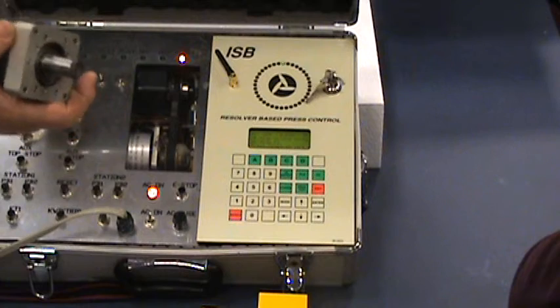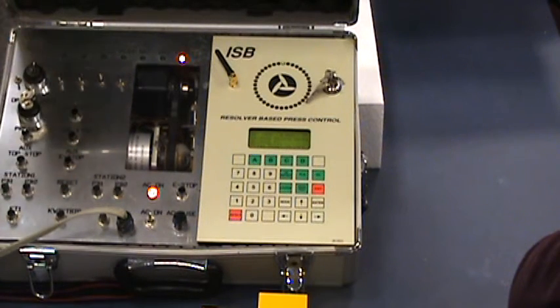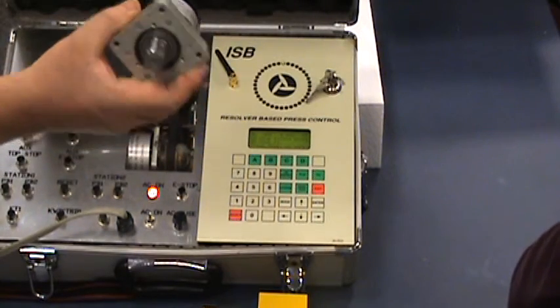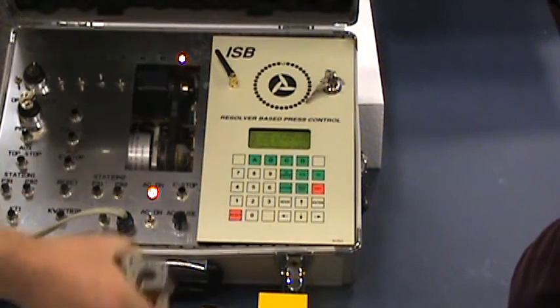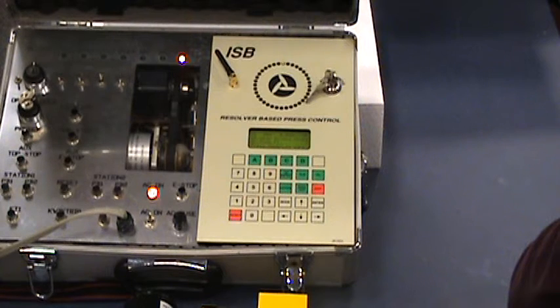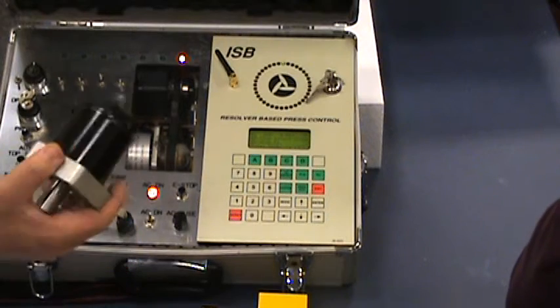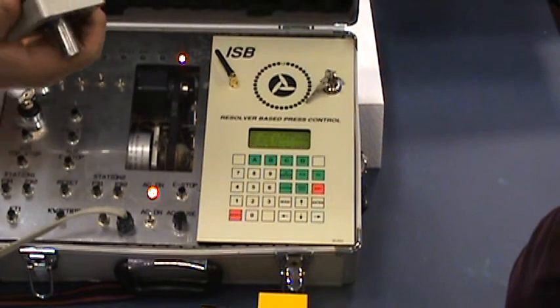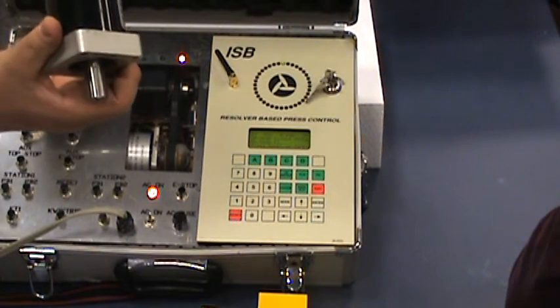So this is why we're relying on the cam box to be your pillow block or create a pillow block arrangement. Or if you're using a rubber timing belt with cog teeth, there's never going to be enough axial load on a three eighths inch resolver. But anything else, Lovejoy coupler, sprocket and chain drive, where you're direct coupled to the end of the shaft, you definitely want to go with this, because this can handle in excess of a hundred pounds of axial load. The bearing is just that much more massive. You can help yourself by mounting these on spring-loaded bases, so you're minimizing some of the effect. But under a normal installation, this would be a pretty bulletproof resolver to be using.